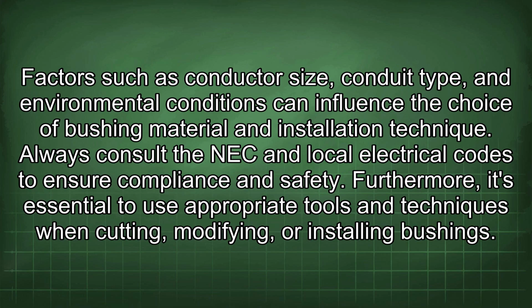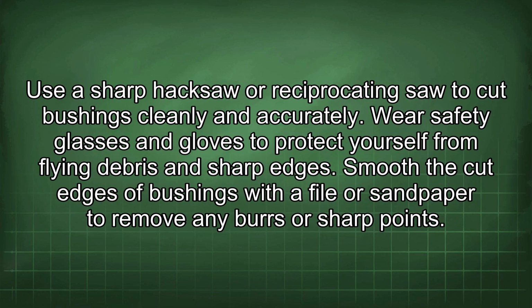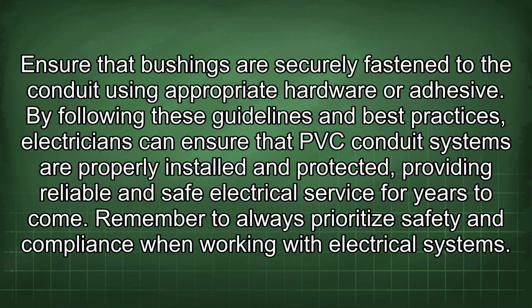Furthermore, it's essential to use appropriate tools and techniques when cutting, modifying, or installing bushings. Use a sharp hacksaw or reciprocating saw to cut bushings cleanly and accurately. Wear safety glasses and gloves to protect yourself from flying debris and sharp edges. Smooth the cut edges of bushings with a file or sandpaper to remove any burrs or sharp points. Ensure that bushings are securely fastened to the conduit using appropriate hardware or adhesive.